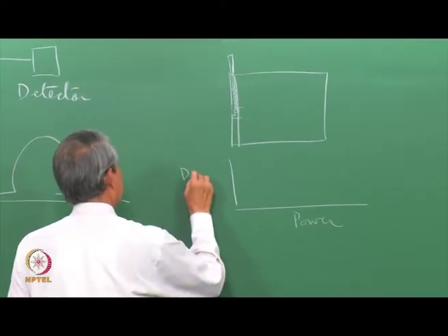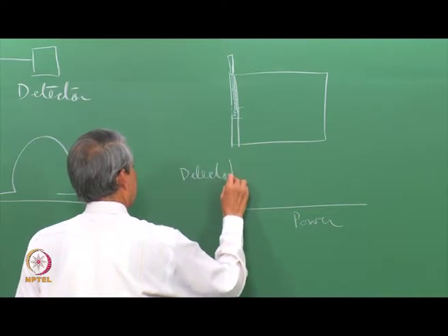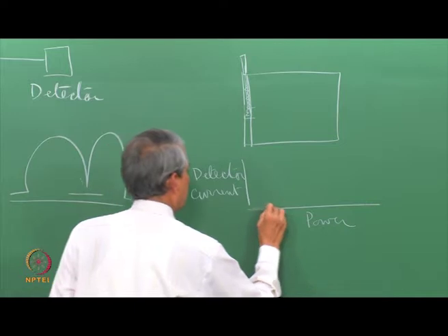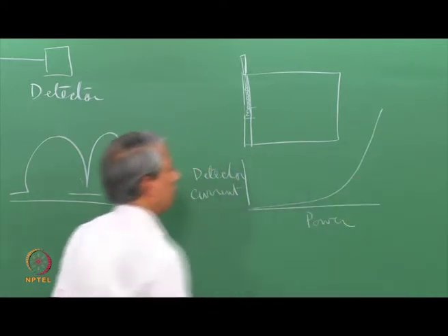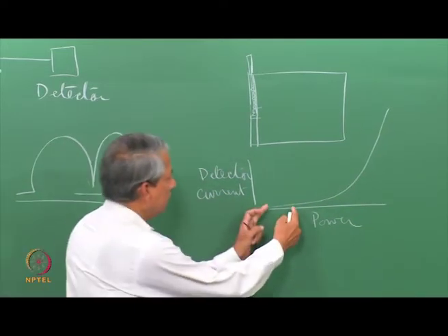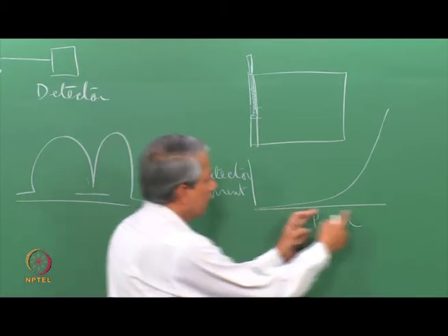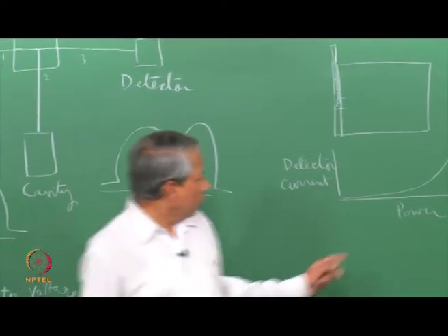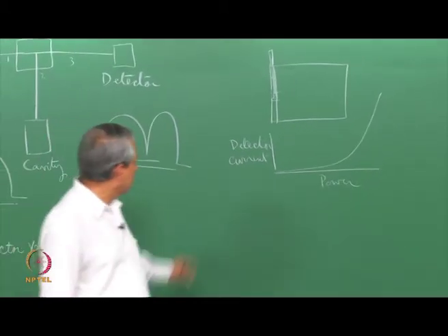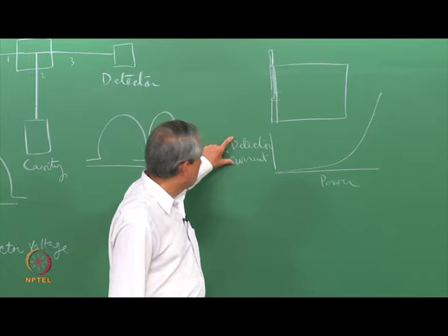Current, which looks something like this. So, when the power is very small, it is very insensitive, and somewhere here it is more sensitive, that we saw in our last lecture. So, we want to have a sensitive spectrometer, so that a small change in microwave because of the EPR absorption can be detected much more conveniently.